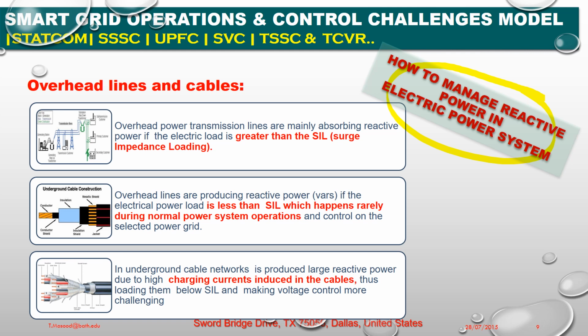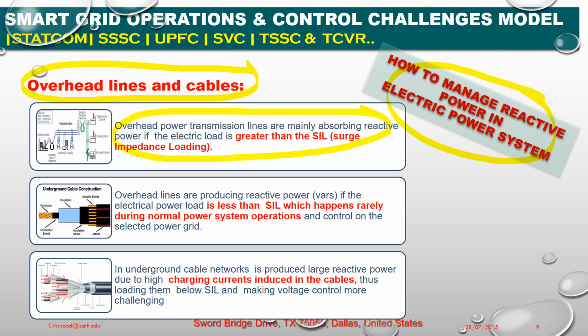First, overhead lines and cables behavior. Number 1, we need to understand: overhead power transmission lines mainly absorb reactive power if the electric load is greater than the SIL, surge impedance loading. So certainly the load is all the time above the SIL.